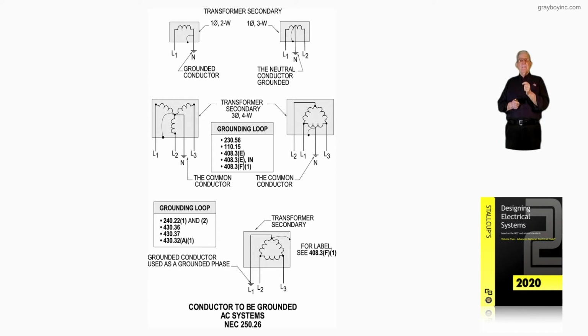Now over to the right, I have a three-wire system. I have a 240-volt coil tapped in the center, and it's a neutral. It carries the unbalanced current. Again, I'm a little repetitious here, but I have to look at it. Maybe you just looked at this illustration only. So if you had L1, 100 amps, L2, 80 amps, the neutral is 20 amps. But if you had, say, 90 amps on L1, 90 amps on L2, there's no unbalanced current. The neutral would see zero, which would be great if you could do that.